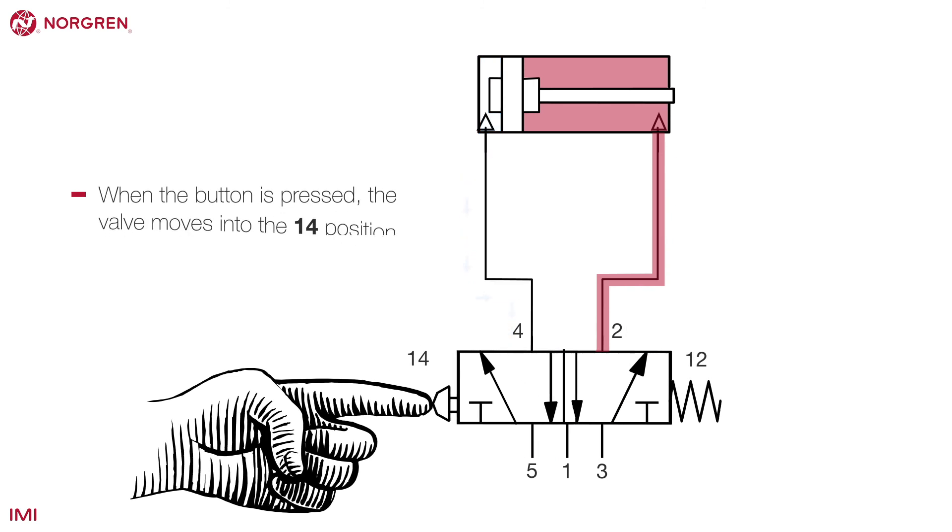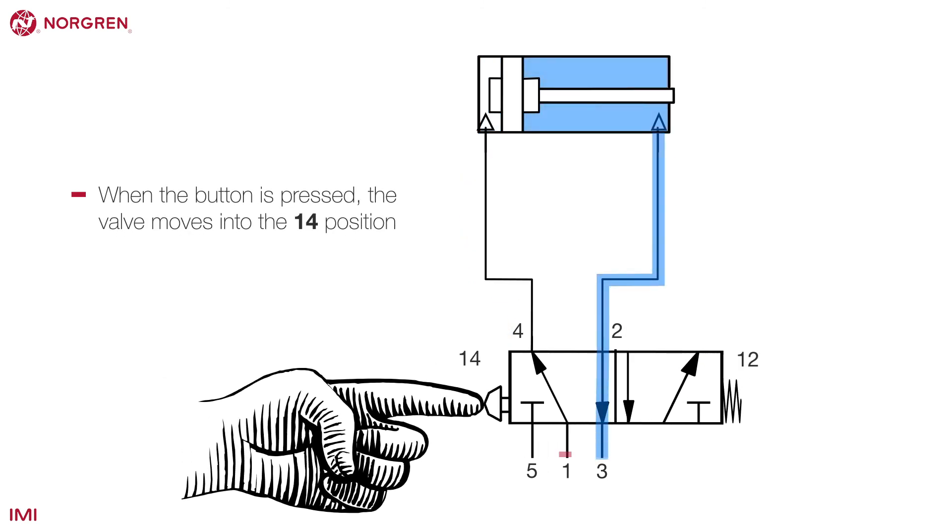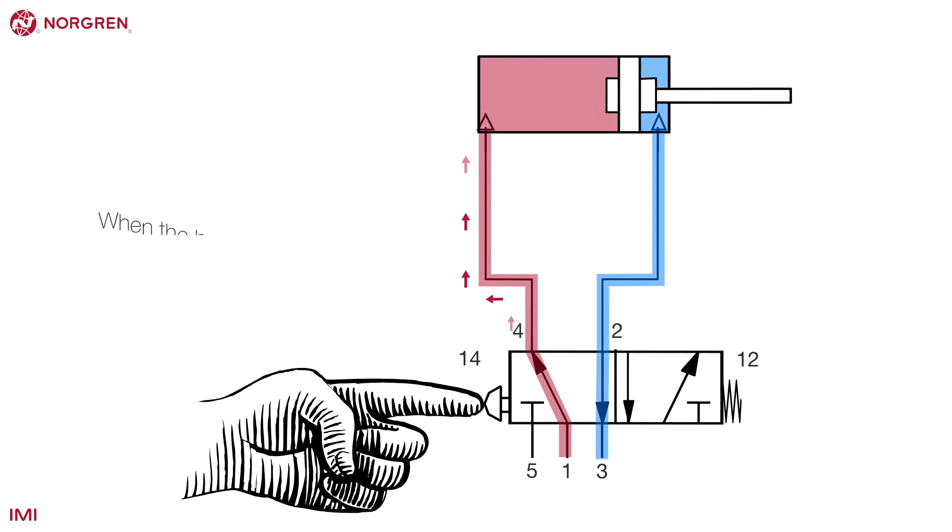When the button is pressed, the valve moves into the 1-4 position. Air now travels from port 4 of the valve to the back of the cylinder, pushing it forwards. The air at the front of the cylinder now passes back through port 2 and out of the exhaust at port 3.